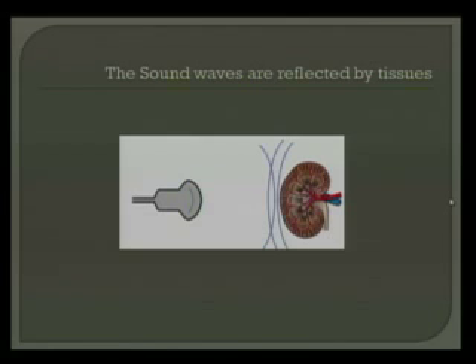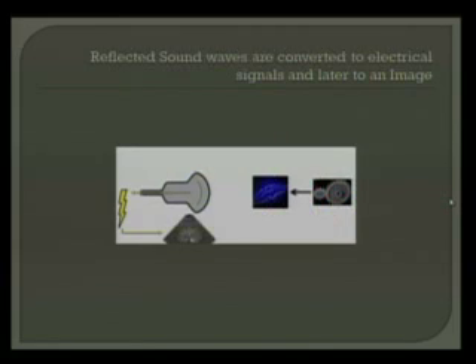Something very similar, that not only the incoming but the outgoing beam is also, the sound waves are reflected by the tissues. As you know, what is coming back from the tissues is what is forming the image. And that is also formed by this. Reflected sound waves are converted to electrical signals and later into an image, right? That makes sense? So electricity into sound, then sound into electricity. So that's what the crystal is doing. And then that electrical energy is manipulated by the system, the ultrasound machine, into an image.